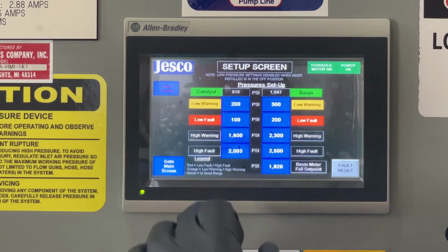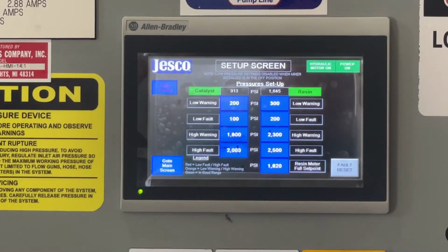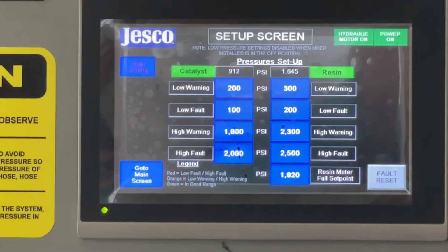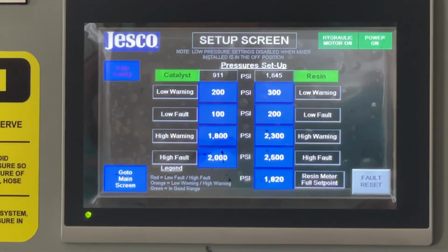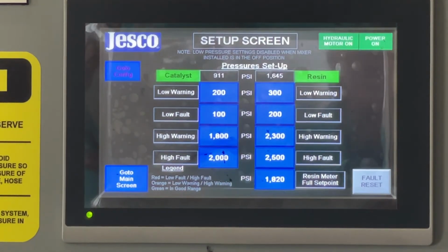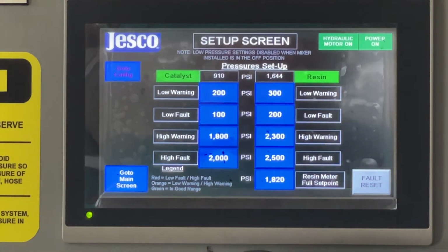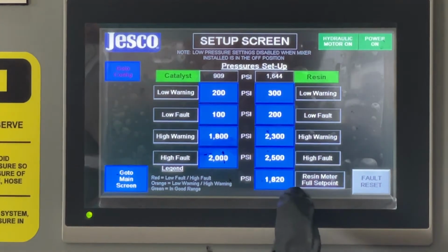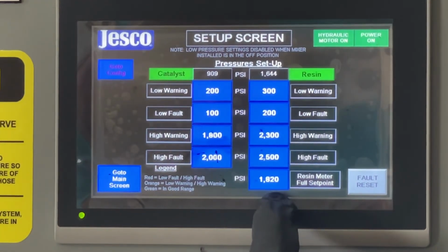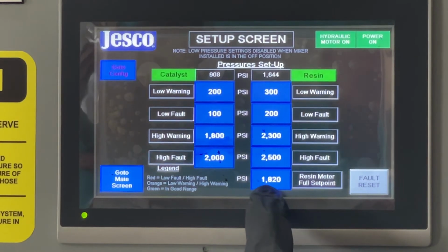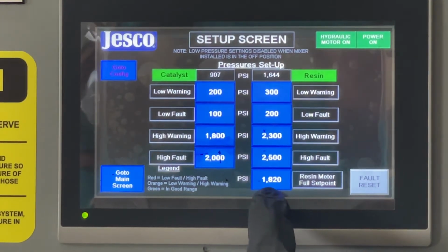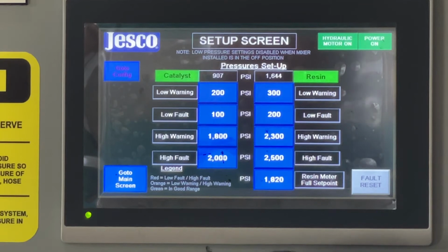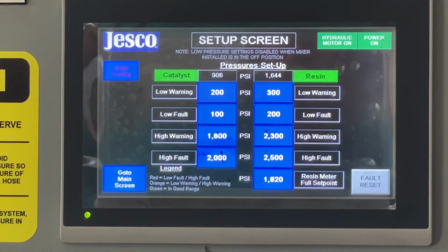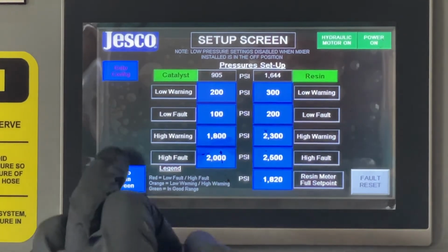Once you enter the password, you go to the pressure setup screen, and this allows you to change the high-low warnings and the high-low faults for both the catalyst and the resin, which is read at the pressure transducers. We also have a resin meter full set point, which is looking at the resin side transducer. By adjusting that, it allows the system to build sufficient pressure for optimum performance at every dispense.